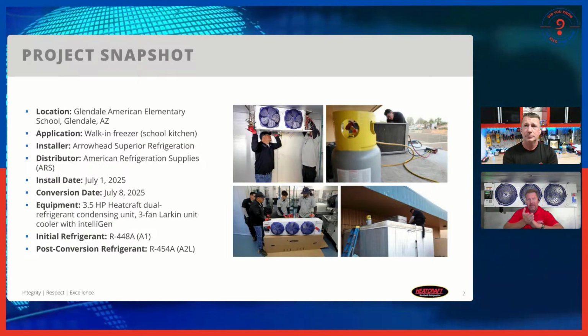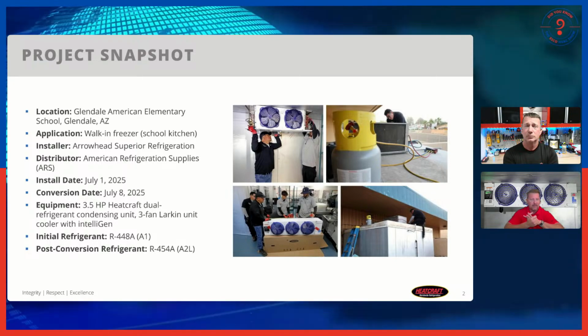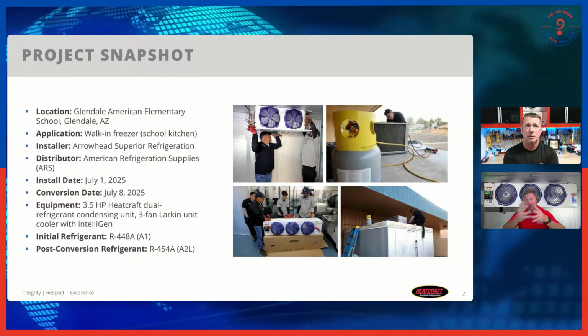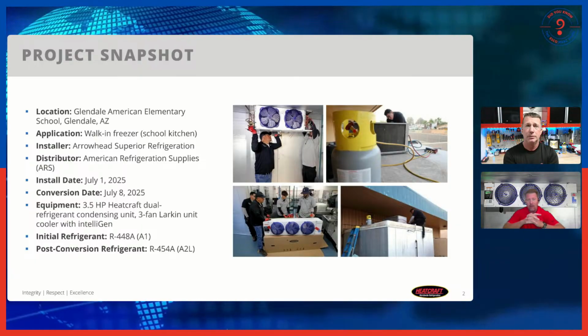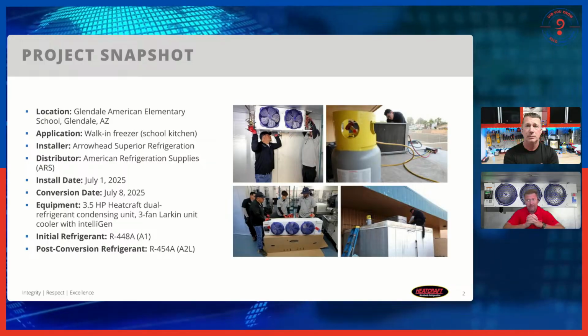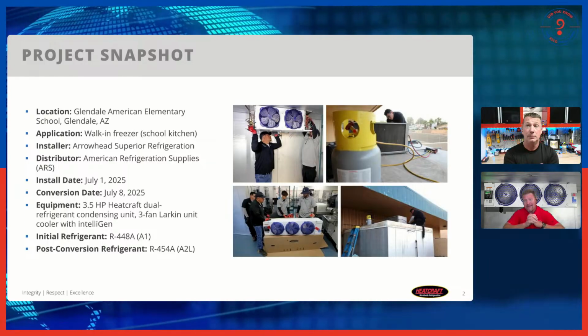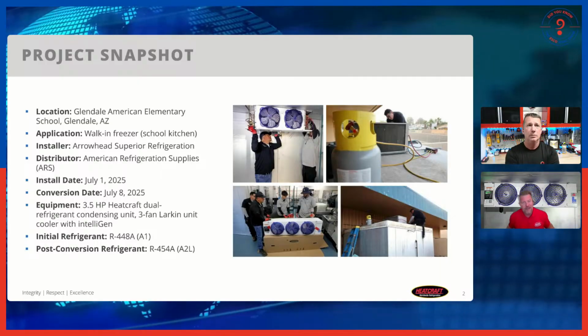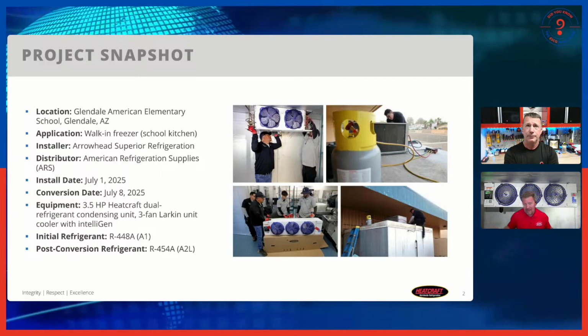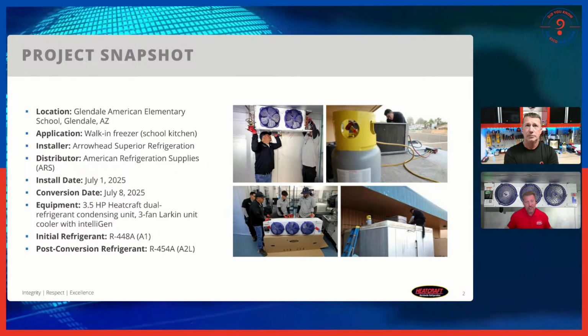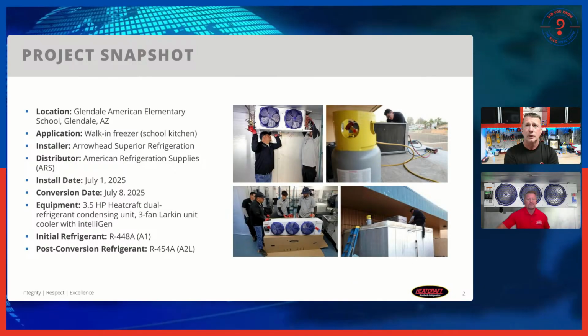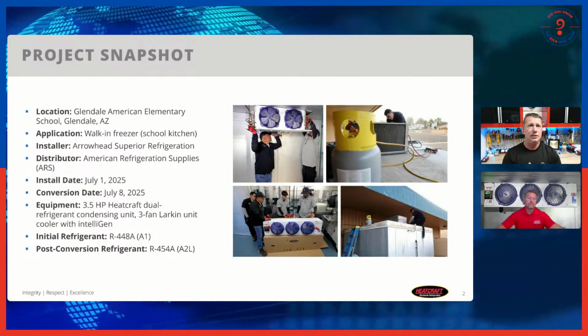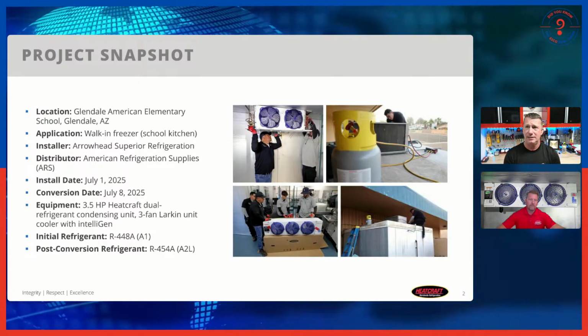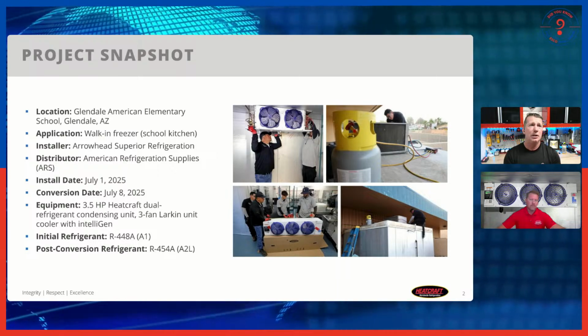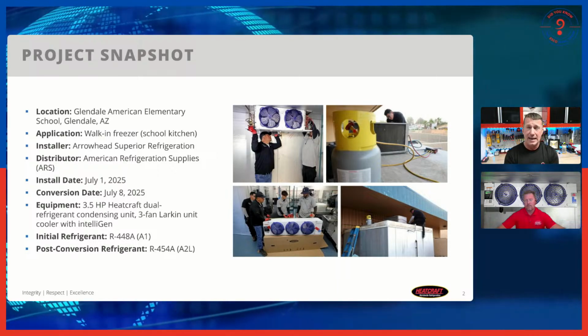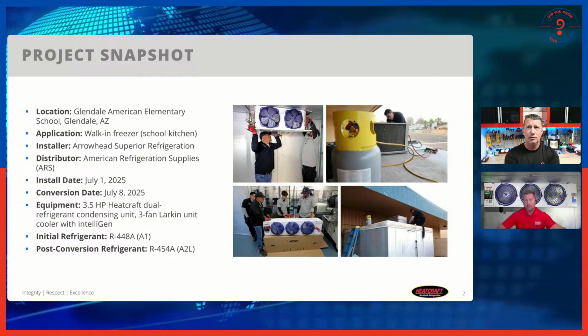By the time I had gotten there, they had removed the old system. They were in the process of hanging the new evaporator coil, and it was already in the 90s, and that was at 7:45 in the morning. Keep in mind the freezer had been shut down at that point because it was not during the school season, so it was just as warm in that walk-in freezer. So we're taking out a two fan R448 system, and we're now going to be installing a 454A A2L.